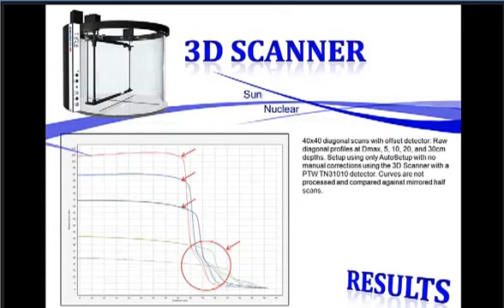And so these asymmetries are asymmetries that you do see in your primary collimators. When we do our commissioning, we wanted to test that. We scanned a full profile. And then what we did is we took that same profile, copied it in the system, mirrored half the profile to see what we would have had versus what we actually scanned. You can see some differences. The arrows show you some differences where if you would have done a symmetry, a mirroring of the profile, that you would have missed some of the finer detail in those profiles. The significance of that in your planning system is completely up to you. I've been told that we are fairly anal when it comes to some things and that they probably don't make a whole lot of difference. But the fact that we can see this data is something that as physicists, I feel we should at least be able to evaluate and be able to determine whether it's significant or not rather than just assuming a mirror profile is okay. We tested all these functionalities during our first commissioning and actually was very impressed with the ability for us to get the data in a very timely and quick fashion.